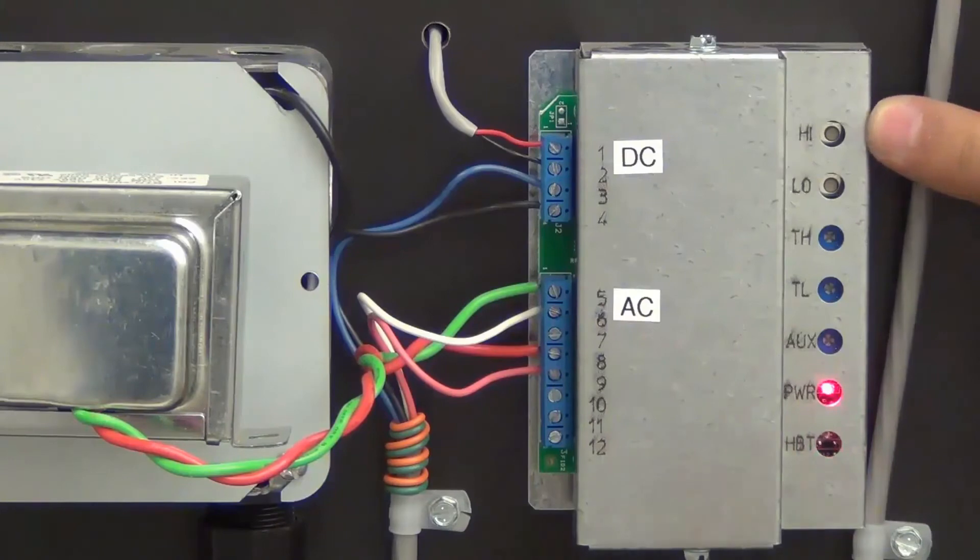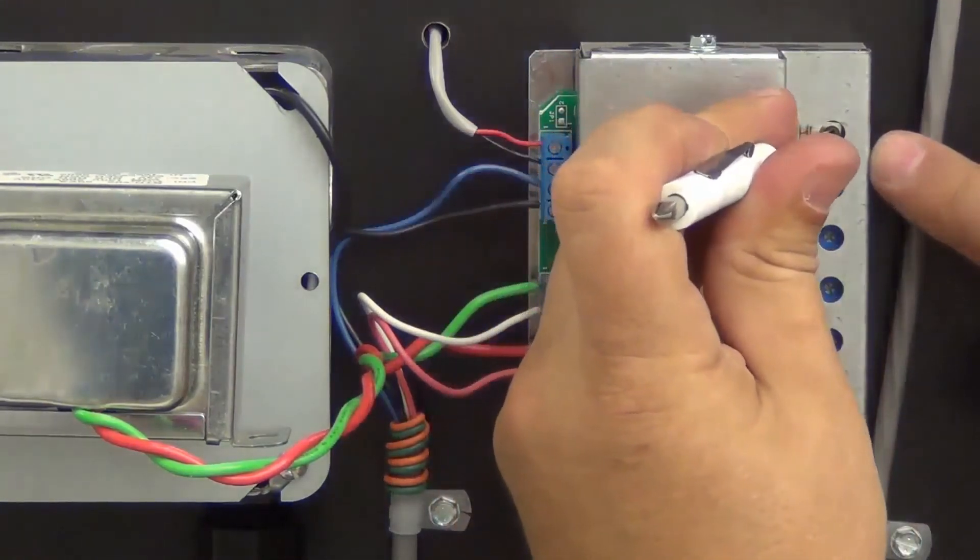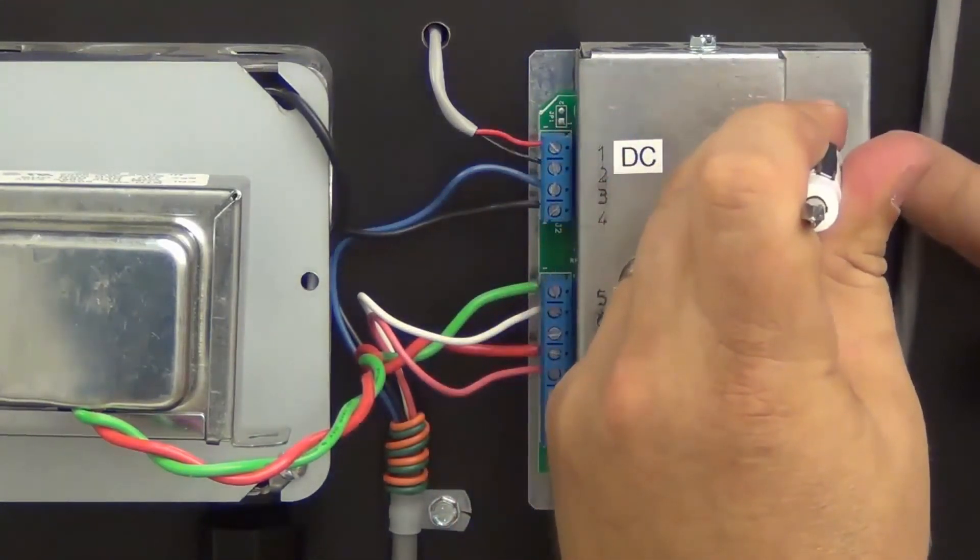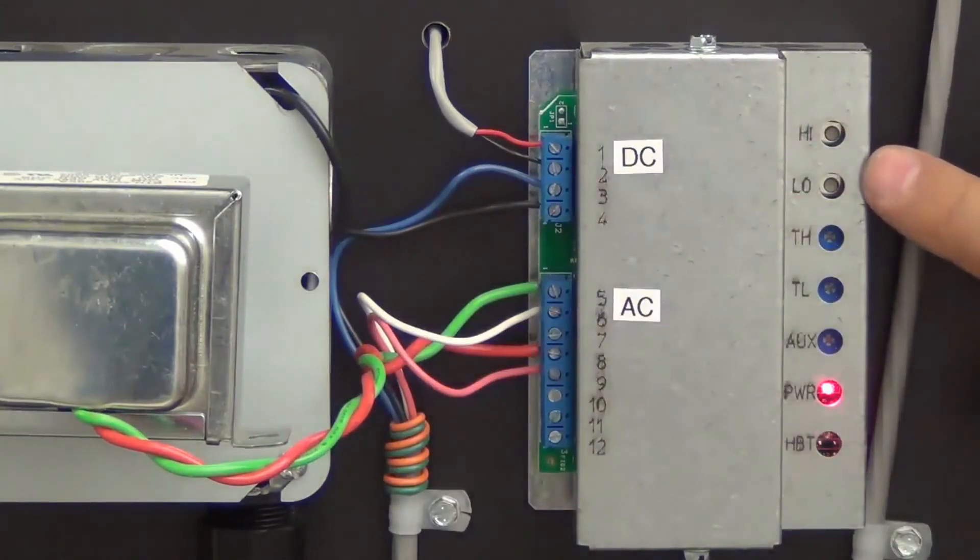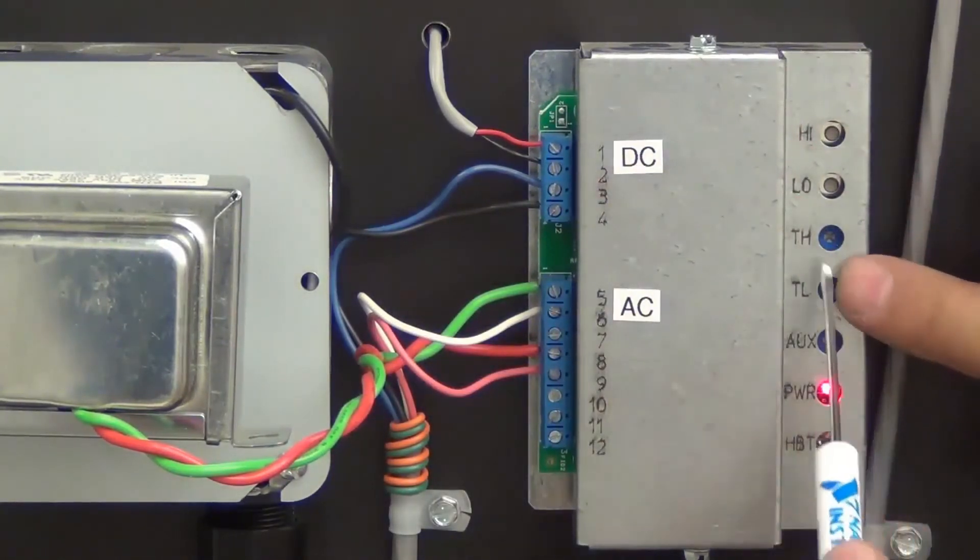Turn on the exhaust fan to high. On the controller, push in the high button for a couple of seconds. Adjust the high trim pot to match the exhaust airflow.